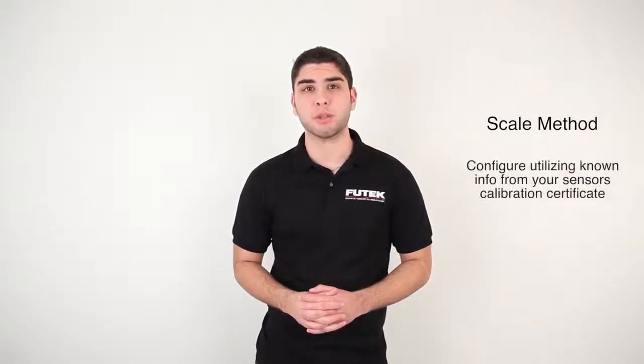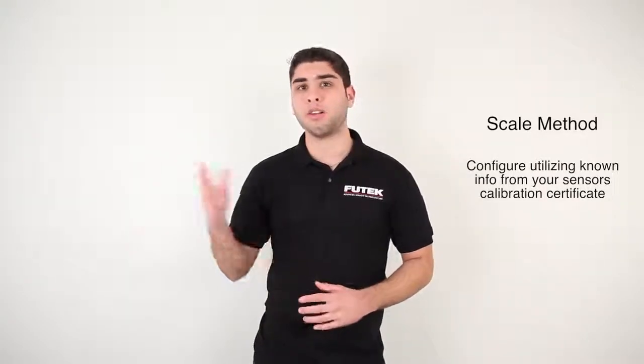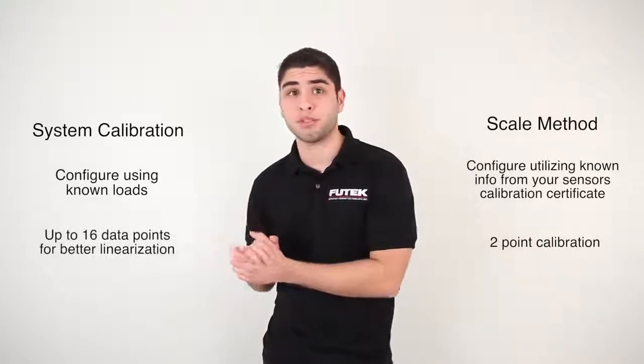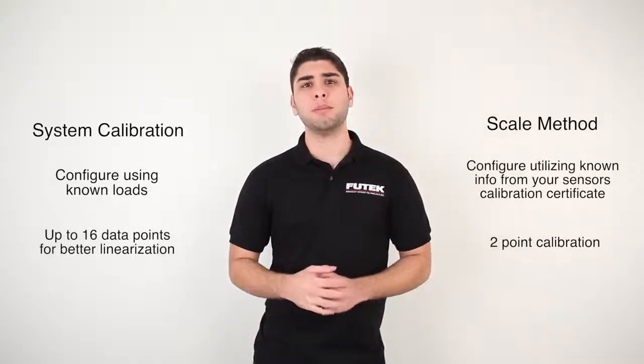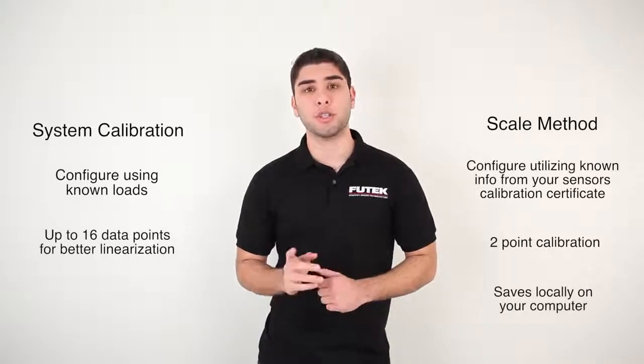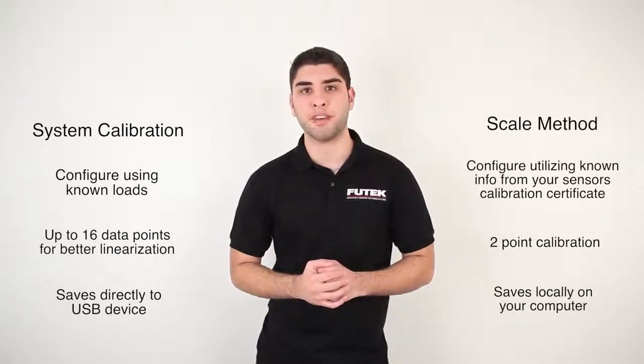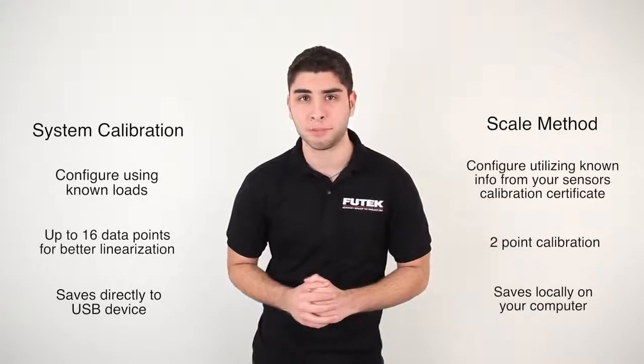How can you easily decide which configuration is right for you? Just consider the following features of each configuration. The scale method will allow you to configure sensors utilizing known information from your sensor's calibration certificate. On the other hand, a system calibration will allow you to perform a calibration using known loads. The scale method utilizes a two-point calibration, while the system calibration utilizes up to 16 data points for better sensor linearization. The scale method saves the calibration information locally on your computer, and the system calibration saves it internally in the USB device, making it a plug-and-play system.